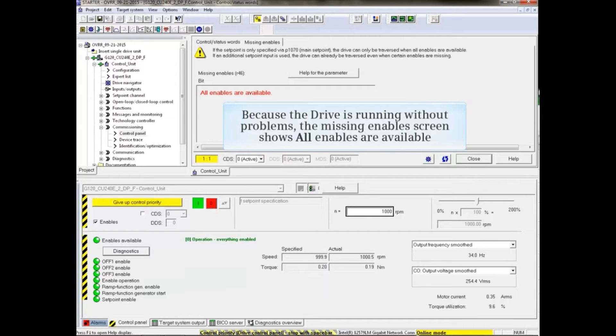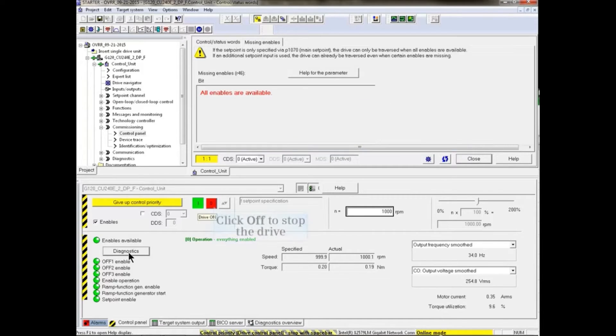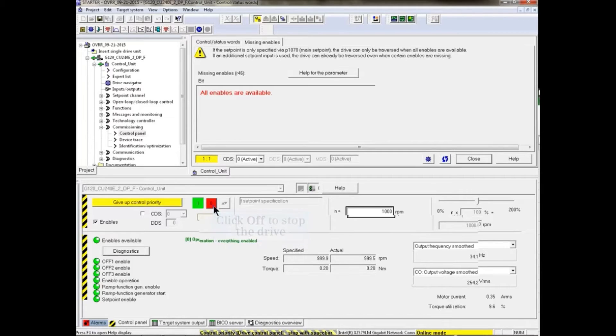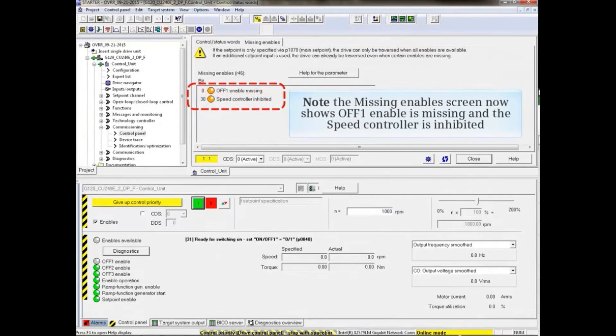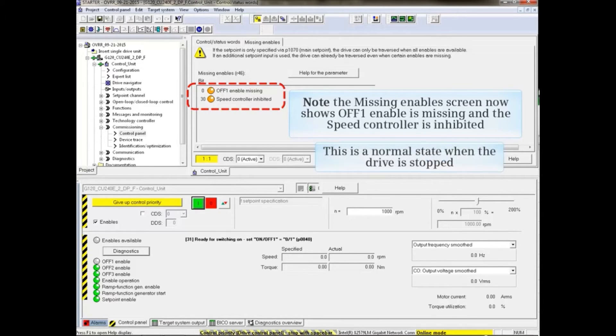Because the drive is running without problems, the Missing Enables screen shows that all Enables are available. Click the red Off button to stop the drive. Note the Missing Enables screen now shows that Off 1 Enable is missing and that the speed controller is inhibited, in normal state when the drive is stopped.